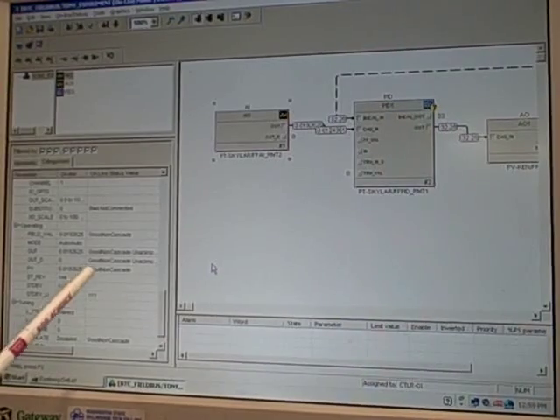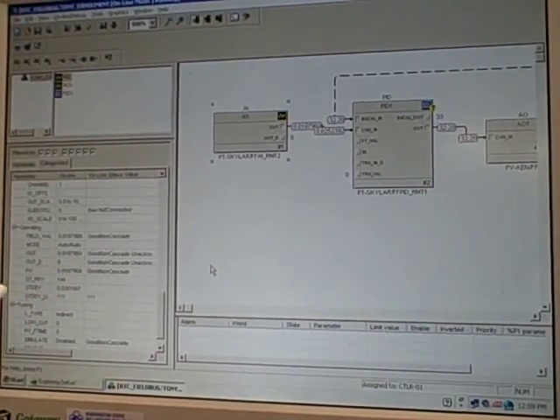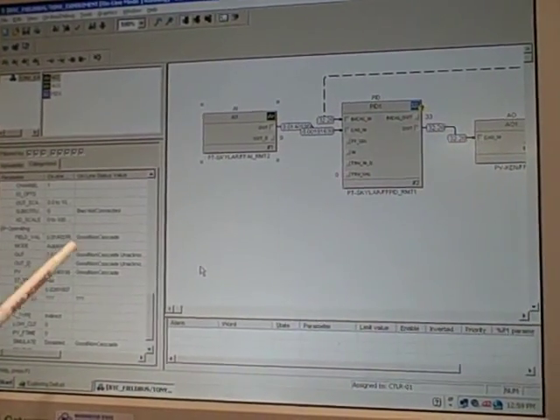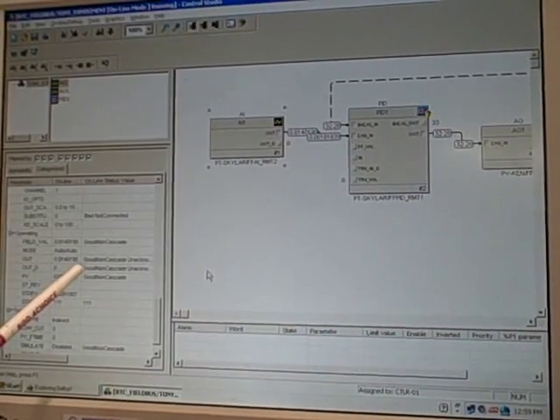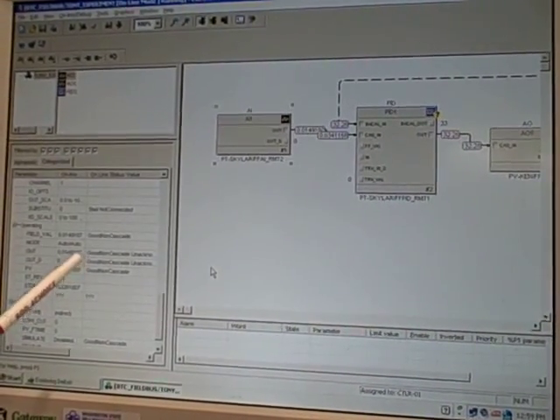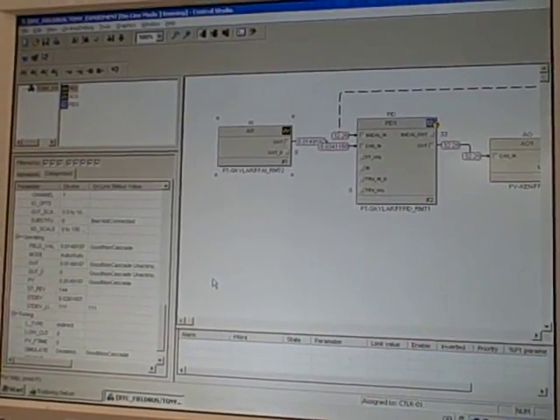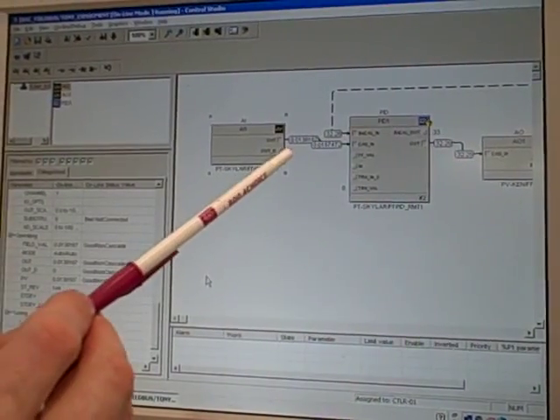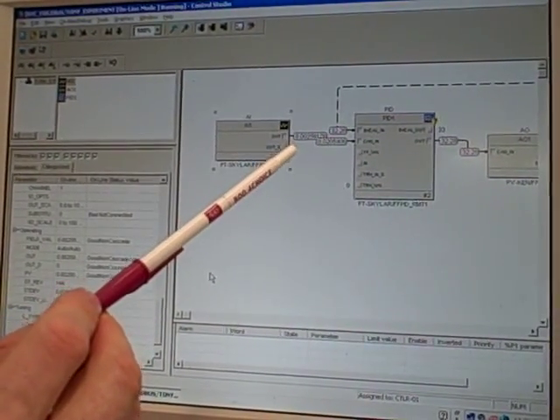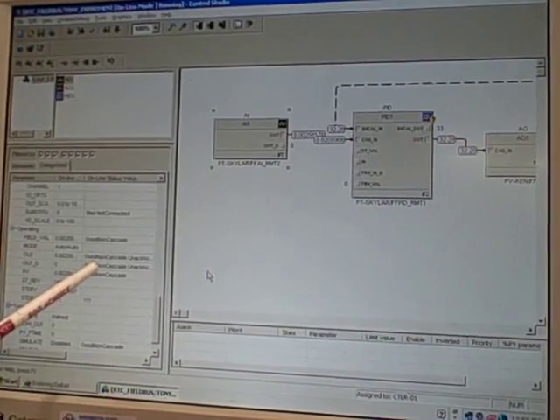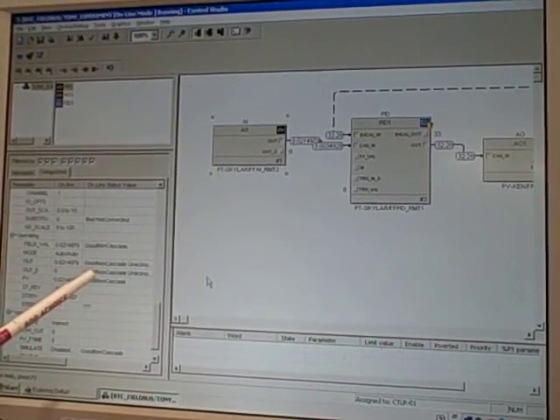A status saying hey, I'm not really certain about this. It's going outside of the range we would expect. So this is an indication of what's going on in a fieldbus instrument when you have status attached to the number. And you'll see again when that pops negative, that turns a blue color up here at the question mark, and then over here it will say uncertain.